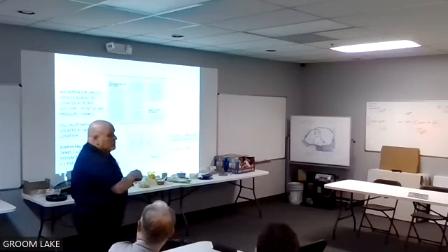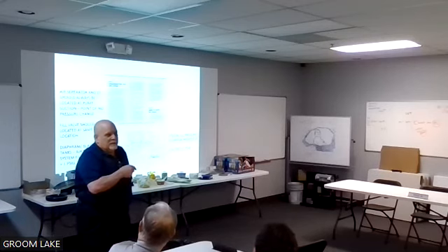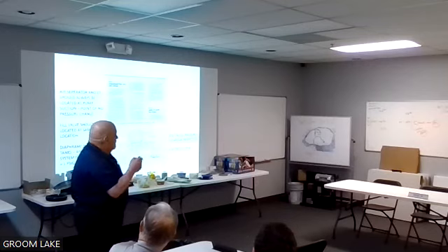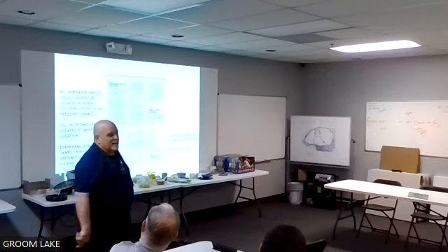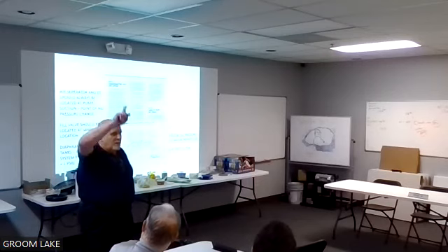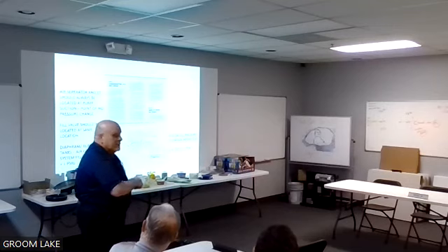But if I put it, most of the equipment rooms go on the top floor, so you don't have to worry about that too much. But the biggest thing is it's all in equilibrium, but this just needs to be higher than the air separator, so the air can rise into that tank. Doesn't necessarily have to be on the top of the building, it just has to be higher elevation.